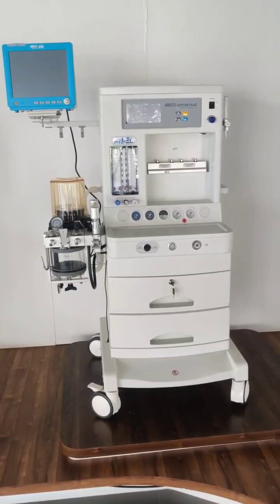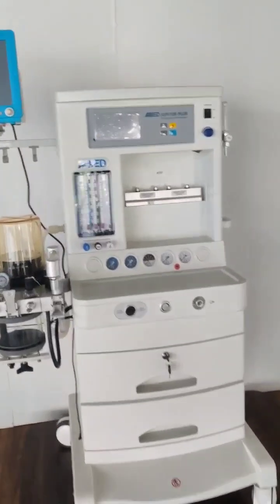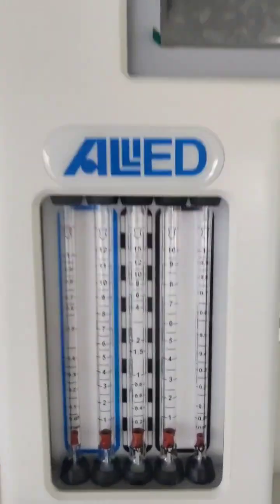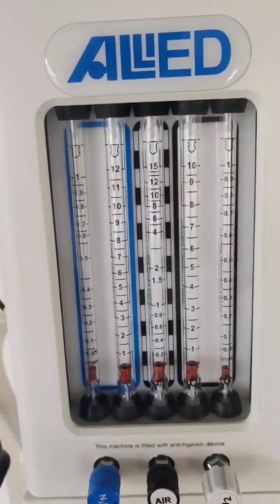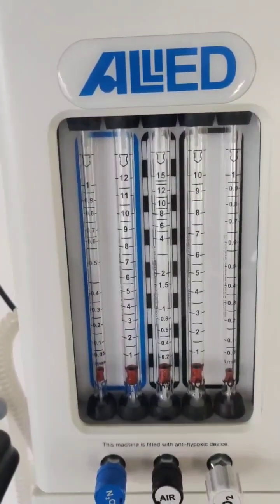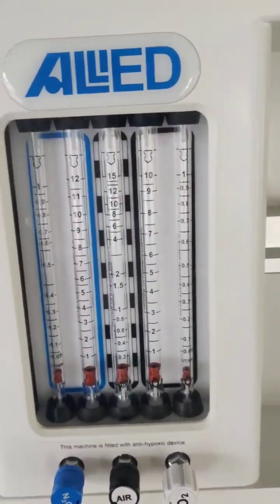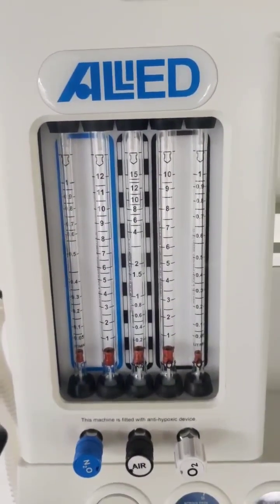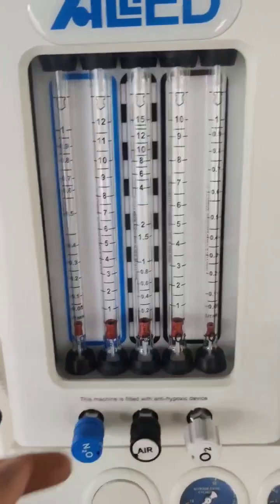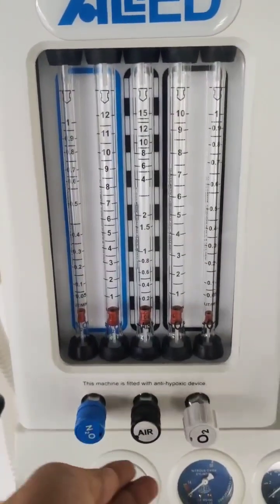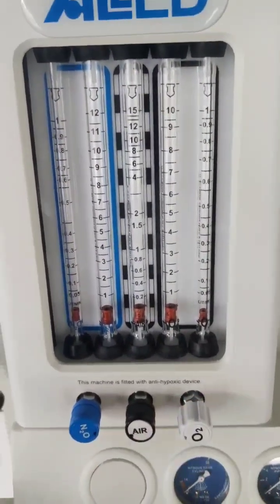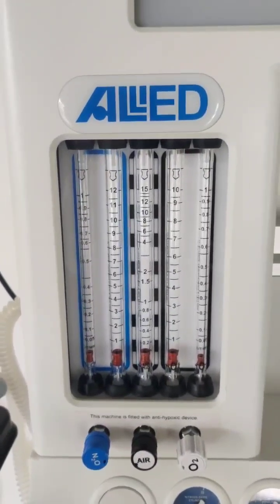Coming to the front side of the machine, we have the flow meters. These are the 5 tube rotameters we are giving: 2 tubes for nitrous oxide, 2 for oxygen and 1 for air. You can set the required flow which is given to the patient with the help of the knobs over here. These knobs are color coded, and they also have the touch coding facility available. This is as per ISO standard.